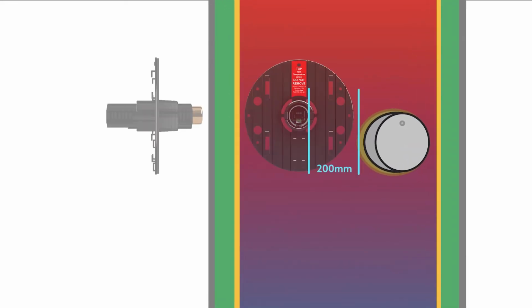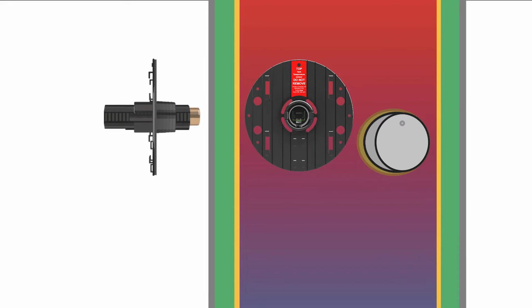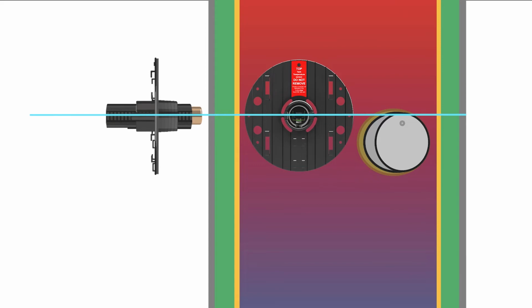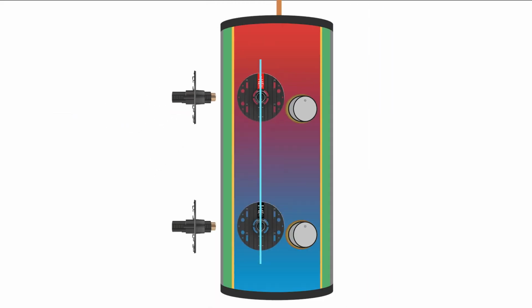The tank probes must not be fitted within 200mm of the nearest edge of an element. The centre of the probe should be level with the uppermost point of the element. The top and bottom probes should be vertically aligned.